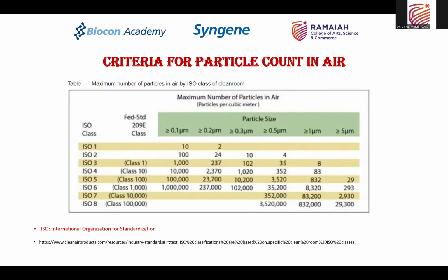What about the larger size, 0.2 micrometer or more? Only 2 particles are allowed maximum in that area. Particles of more than 0.3 micron are not allowed in that ISO 1 standard. So these particles have to be monitored and controlled in these industrial process areas.